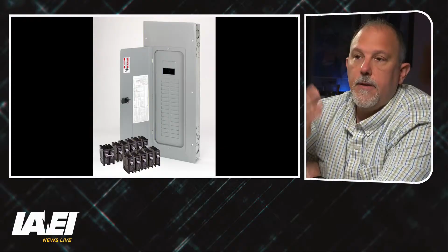What you would do is look at the inside of the door. If I'm out in the field looking at an installation, I'll go to the labeling on the equipment and find out. You'll typically see it's labeled as what it's called: panel board, switchboard, switchgear, industrial control panel, whatever it is, and you'll see the information on the inside of the door. So the first thing you do is look at what is there, then go to the defined terms and understand what that piece of equipment is.